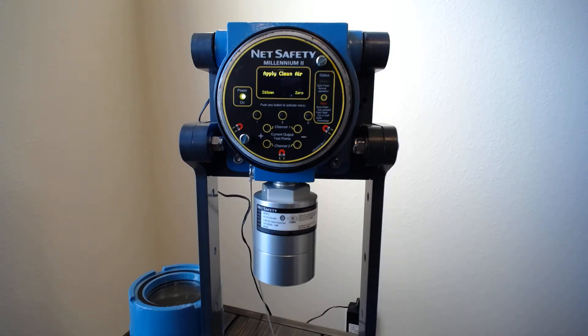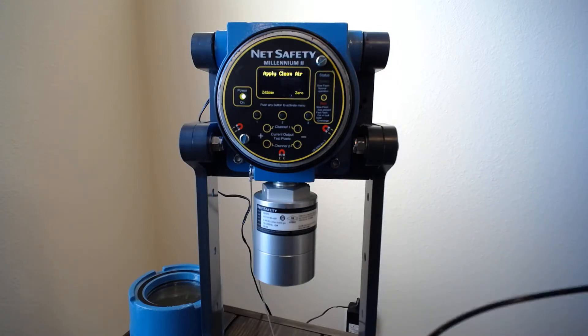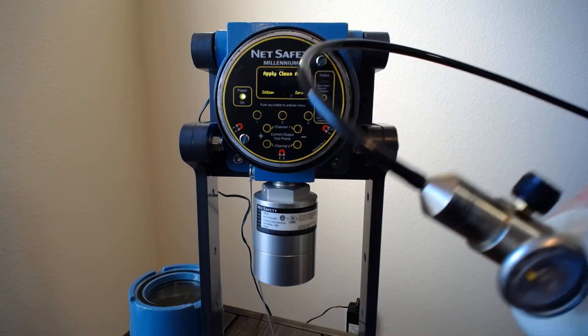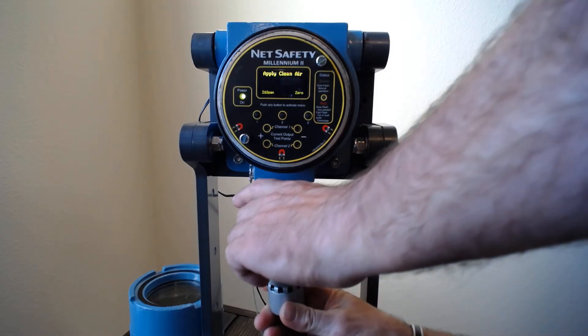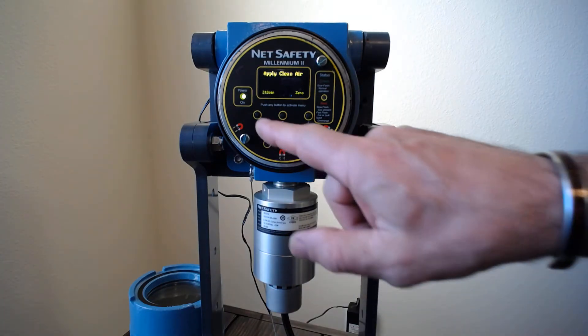It gives you two options: you can zero it, or you can zero and span it. I have the cal adapter attached to a bottle of zero air with a liter-per-minute regulator. I've got two of these set up — one on my zero air bottle and one on my methane. I also have a bottle of 2.5 percent by volume methane, which is 50 percent LEL. You can just swap between the regulators however you want. I'm going to select zero and span.